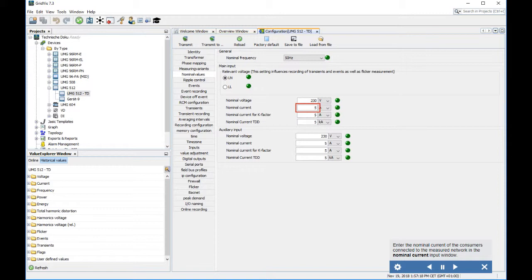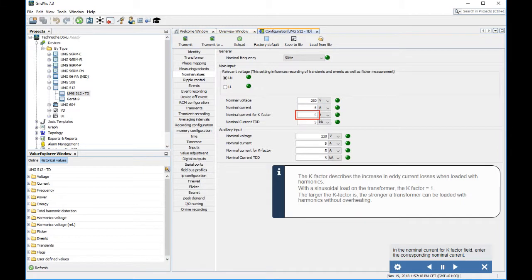The K-factor describes the increase in eddy current losses when loaded with harmonics. With a sinusoidal load on the transformer, the K-factor equals one. The larger the K-factor is, the stronger a transformer can be loaded with harmonics without overheating.